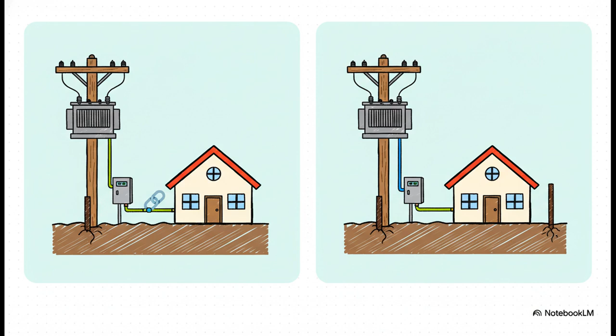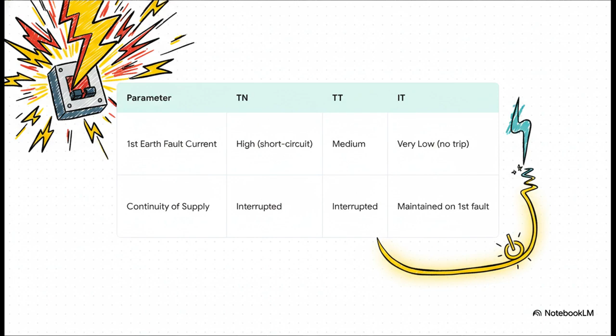And this table here really brings home the main difference in how these systems actually behave in a crisis. Just look at that first row. In a TN system, a fault creates a massive short-circuit current, which trips a breaker instantly. In a TT system, the current's a bit smaller. But look at the IT system. It's the real oddball. On the first fault, the current is super tiny, and get this, the power stays on. And there's a really good reason for that, which we'll get to in a minute.